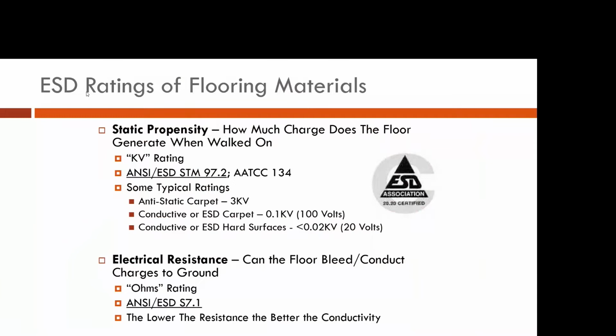In general, according to ANSI standards, anything that is truly ESD rated on the floor will generate less than 100 volts when walking or rolling across it.